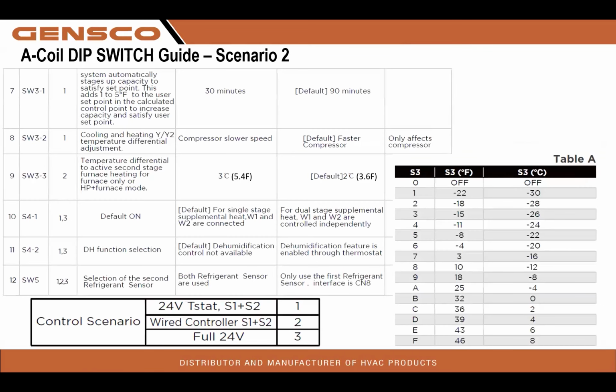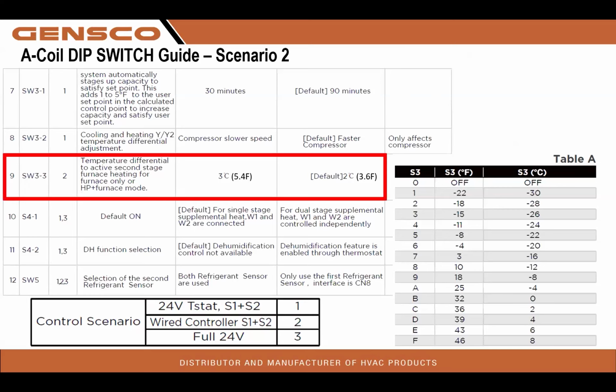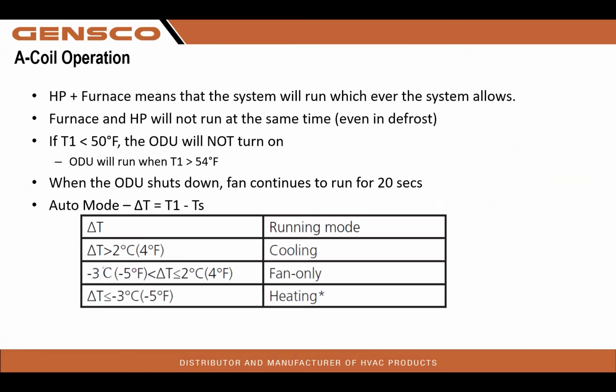More control scenarios, depending on your control scenario, whether you're 24 volt and running S1, S2 out to the outdoor unit, and so forth, refer to your install manual. Dip switch settings are not 100% necessary. We've already talked about SW3-3, temperature control. We're not going to get into a whole bunch of time here, but heat pump and furnace means that the system will run whichever system the system allows. Furnace and heat pump will never run at the same time, even in defrost.